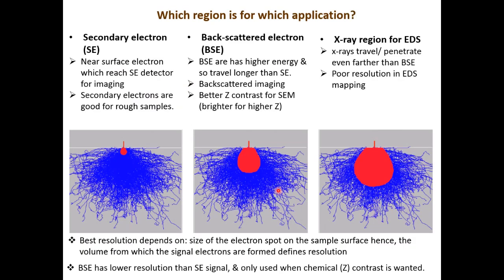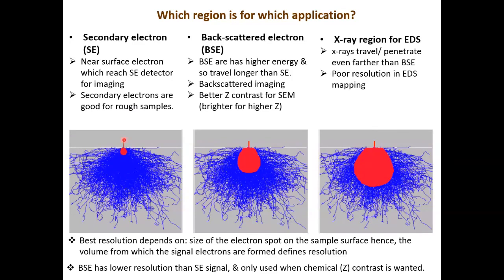As a summary: secondary electrons come from a much lesser depth and lateral spread below the surface, whereas backscattered electrons come from a much greater depth and lateral spread, and characteristic X-rays used for EDS come from even greater depth and lateral spread. So the resolution of imaging goes from best (secondary electron imaging) to poorer (backscattered electron imaging) to not very good (EDS analysis). The resolution is best for secondary electron imaging, not as great for backscattered electrons, and not really great for any imaging or analysis done using EDS.